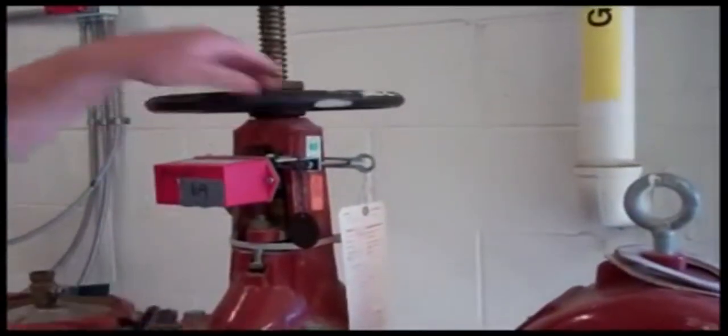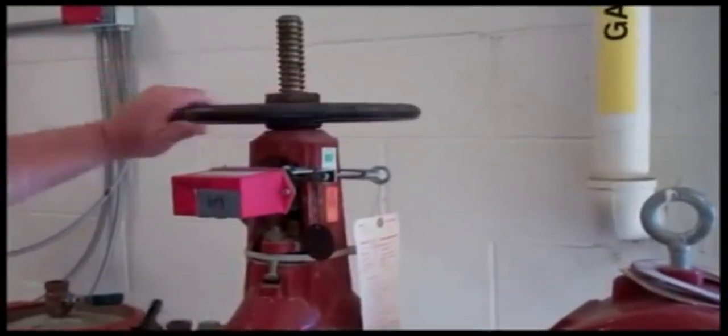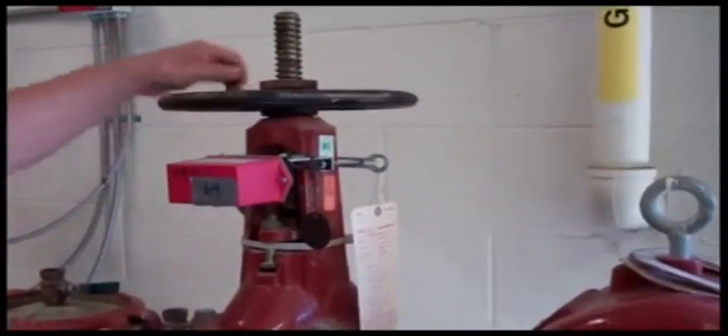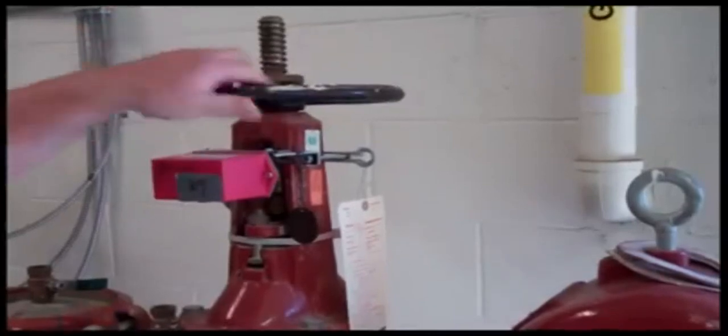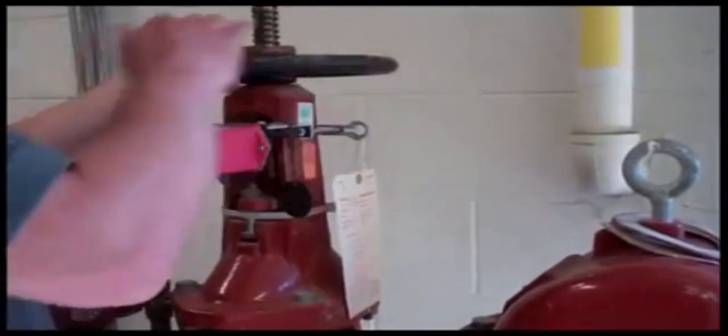Sprinkler tamper switches are designed to notify a fire alarm panel if a valve on a sprinkler alarm system is closed or opened. This is done so that facility managers can know if the sprinkler system has been impaired by having its water supply shut off. These devices are tested by fully exercising the valve through its full range of motion.